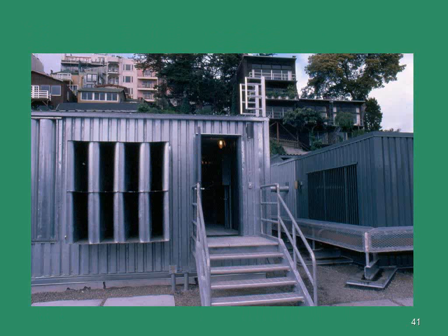This is an acoustical louver, and what it does - it's an airfoil-shaped cross-section. It's perforated, and it's got rock-wool fill, and it's about 42% open area. So the big struggle there was the mechanical designer said, this is a cooling tower, I need gobs of air to make it actually work as a cooling tower instead of just an expensive fan. Yet I had to contain the noise, because you can see through the slide here that this is the property line right at that roof rail. So we had to get air in but contain the noise.